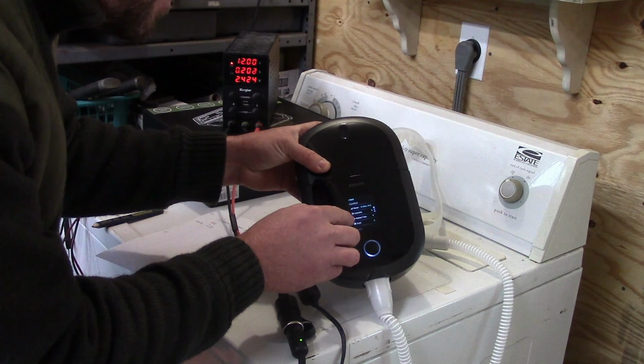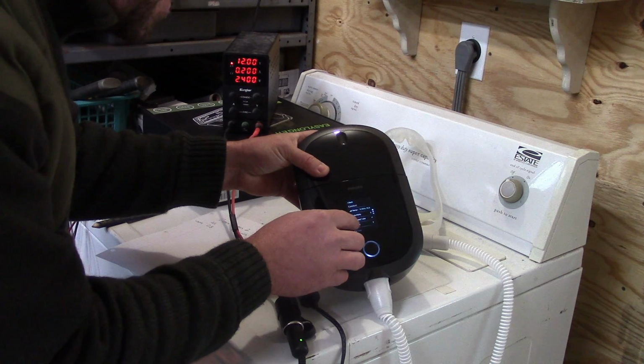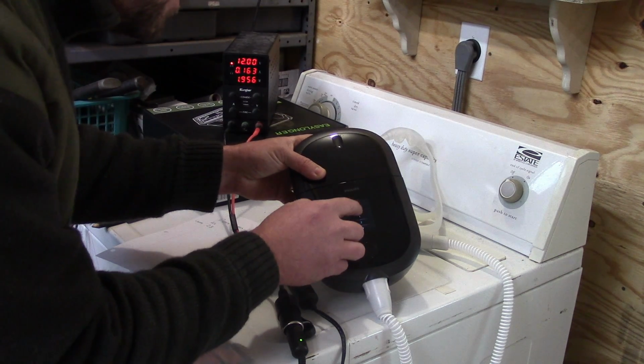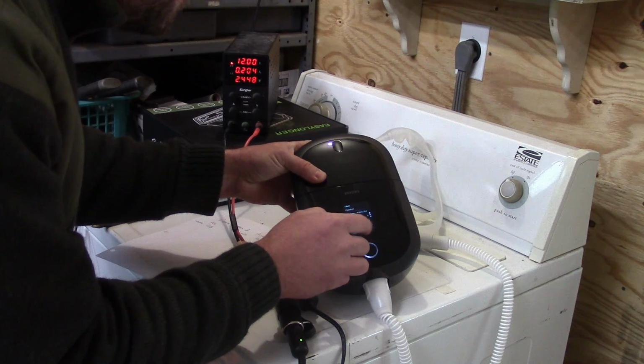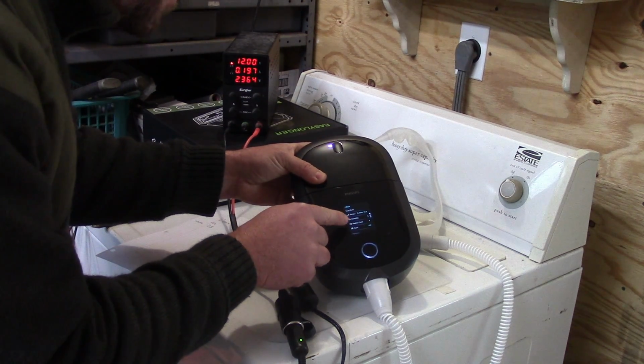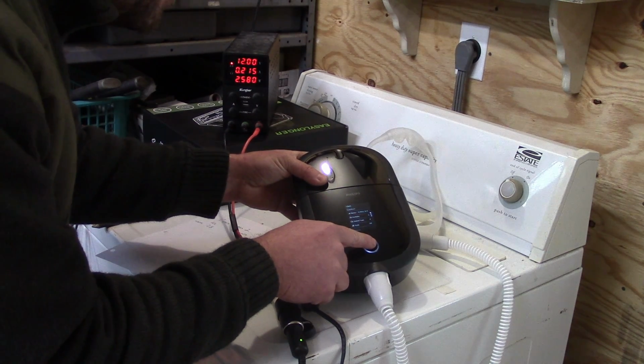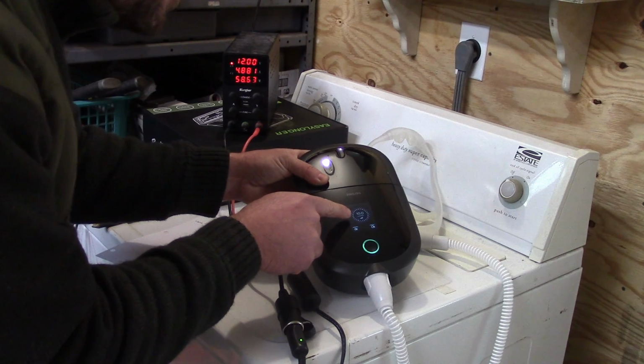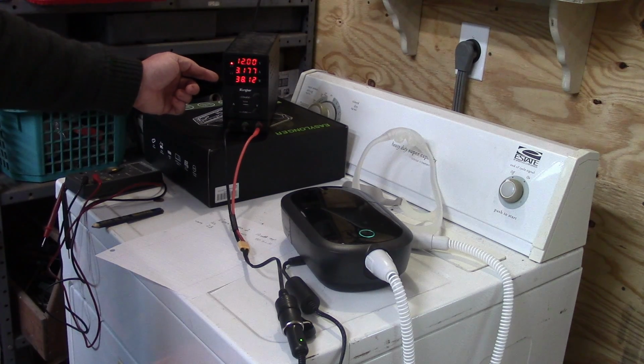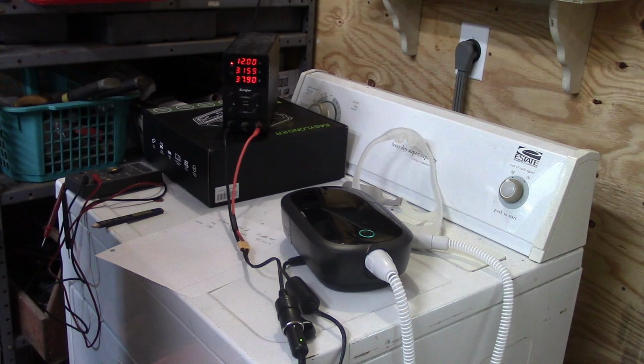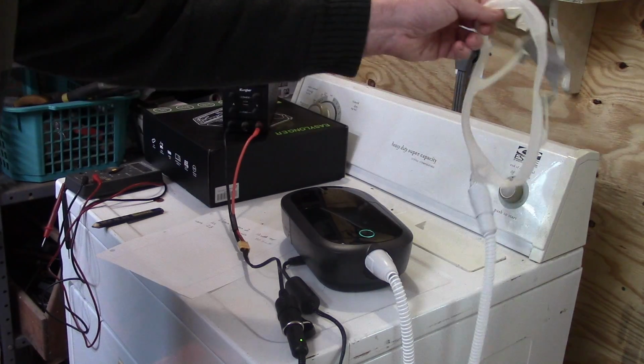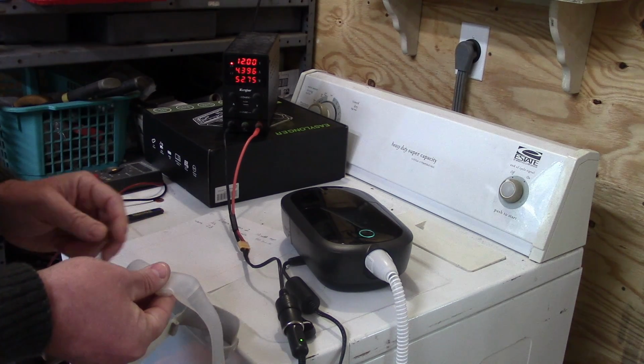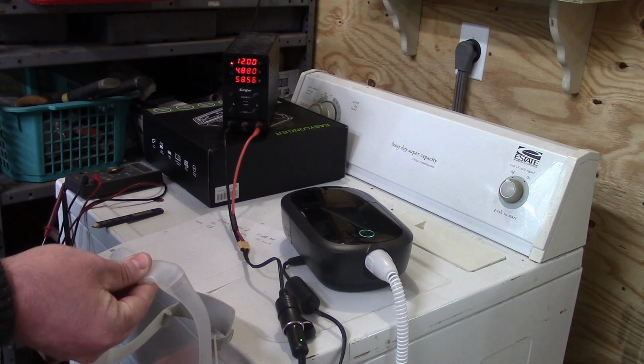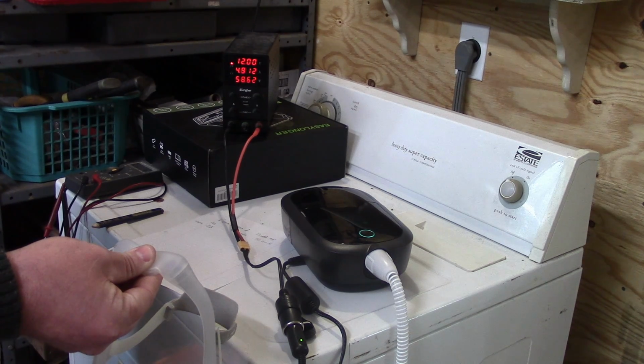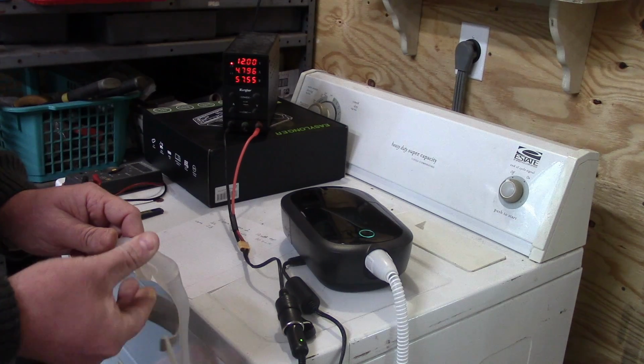Let's look at this together. Humidity at 5, heated tube at 4. And we got flex at 2. I wonder if I can turn that off. Let's turn flex off. Okay, so heat and humidity are on, and my pressure is going to start at 10. So you can see the watts it used has gone way up. We're just under 40 right now, occasionally peaking higher. Let's see what happens if we block the air off. And now the watts go up to just under 60.